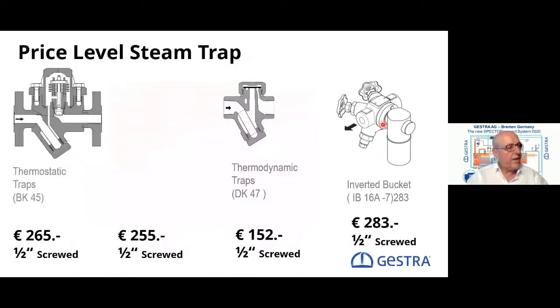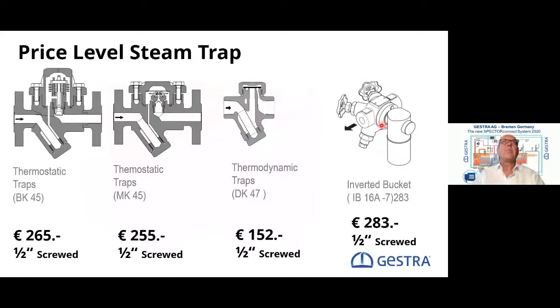Well, the next point is cost of ownership. What does cost of ownership mean? It means the purchasing price, of course, and it means that you also have different costs during the operations. And that I want to show. Here we have an example of the prices, just to show the level difference of the different types of steam traps. We can say that the thermostatic steam traps have a certain level, maybe 250 euros on average. Thermodynamic steam traps are much cheaper, without filter maybe down to 100 euros. And inverted bucket steam traps are going up to maybe 300 euros.